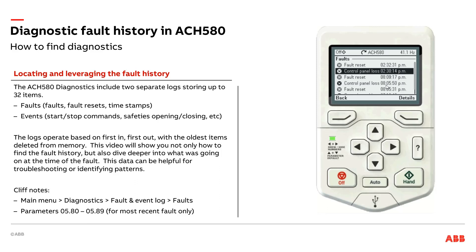If I'm not sure what a control panel loss fault is, I can go ahead and just hit the question mark and it'll tell me what this is. It can also give me some hints and tips on what might have been the problem in the first place. I purposely removed my control panel from the drive while it was running in hand mode. However, if this had intermittently happened, maybe somebody had a bad connector between the control panel and the drive. So it gives you some tips and hints there.